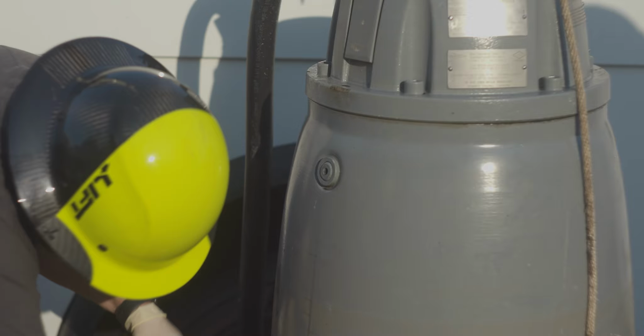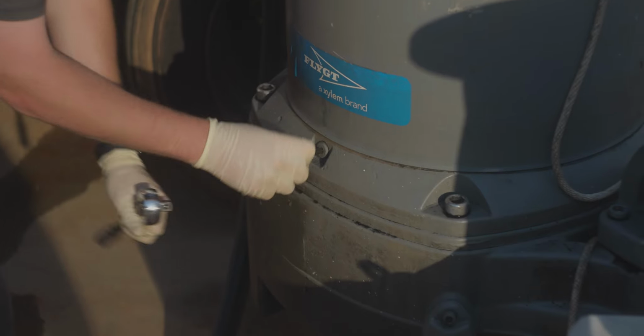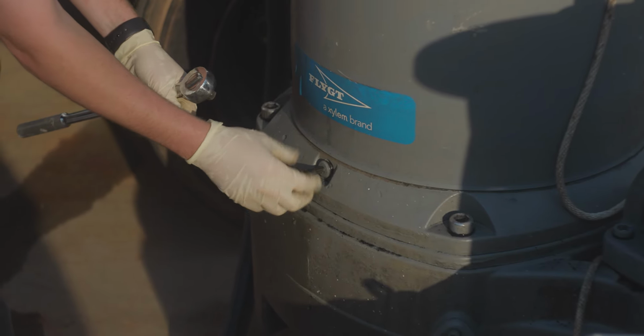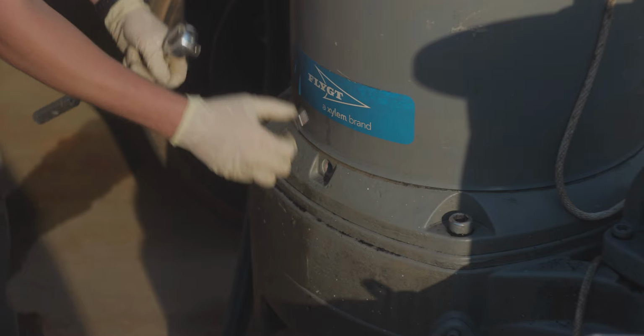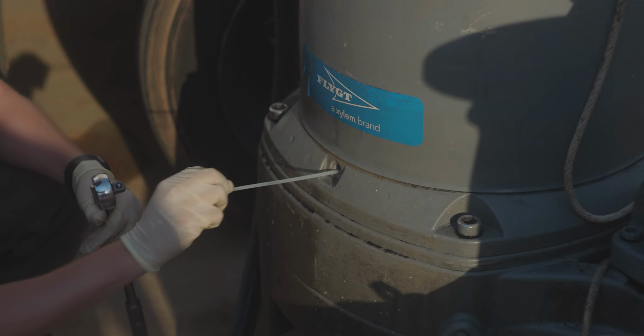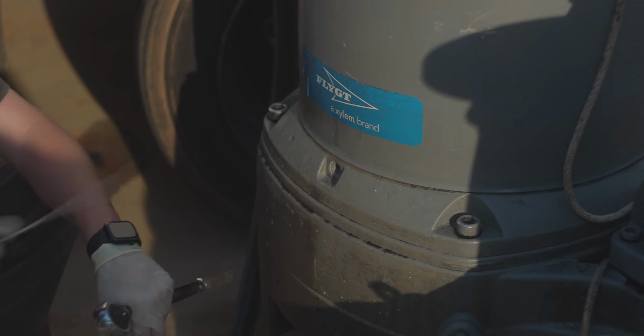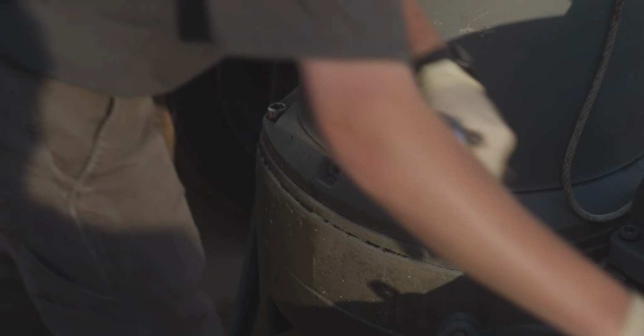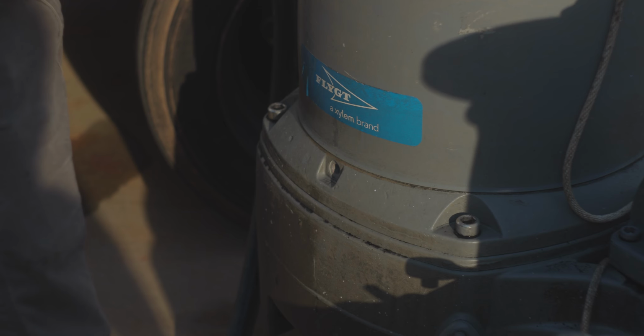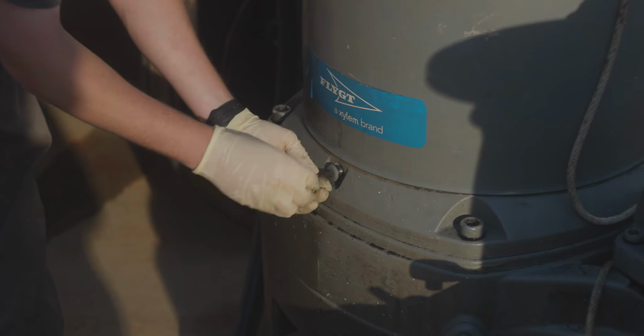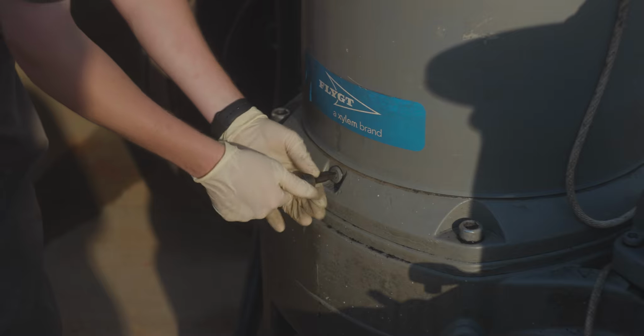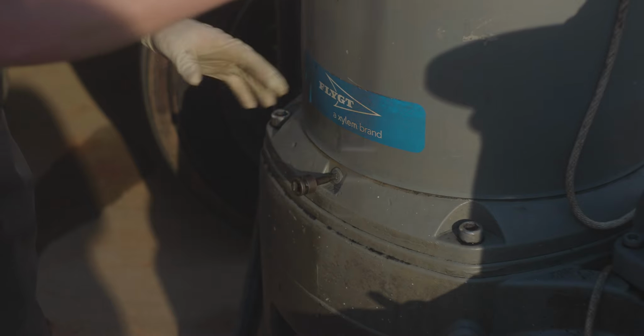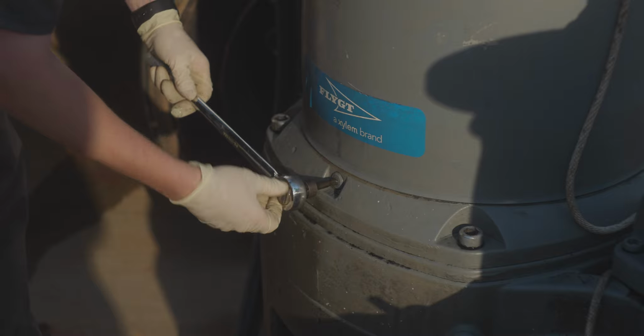Okay, so what he's checking now is the stator housing. The stator housing shouldn't have any fluid in it whatsoever, so he opened up the stator housing to make sure there's no fluid in it, no sign of any leak. There's no oil in the stator housing or anything, so it should be dry. Over time, it will accumulate some fluid just because seals vibrate, so you do get some pass through in there, and every once in a while you have to drain it and then do a seal test on it where we pump up the housing to about 15 pounds and make sure it holds.